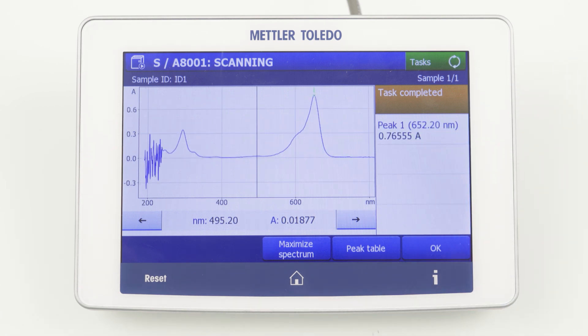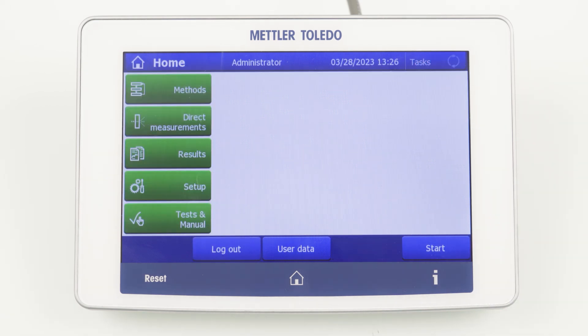The found peak maximum can be used, for example, in a next quant method to record a calibration curve to quantify PFAS. I hope this short video was helpful in understanding how to set up a scan method with various additional settings. The workflow is always the same, independent from your application. Thank you for watching and don't miss our other videos explaining more measurement categories and how to get predefined methods from our application library on MT.com.